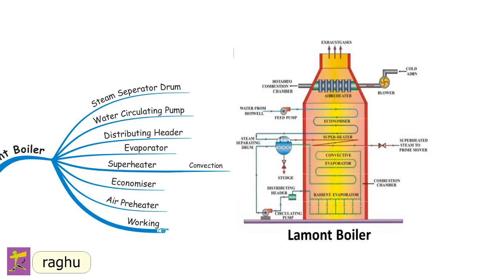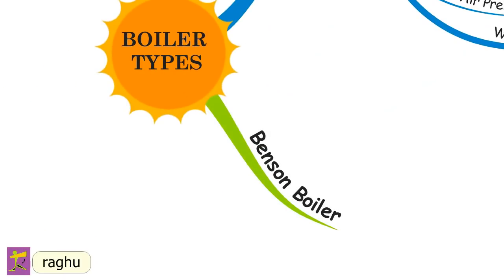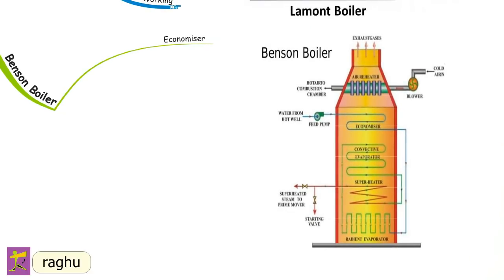In the La Mont boiler, the main difficulty experienced is the formation and attachment of bubbles on the inner surfaces of heating tubes. These attached bubbles reduce heat flow and steam generation by offering higher thermal resistance than a water film. This difficulty is overcome in the Benson boiler, which is the first type of drumless boiler — also called a once-through boiler. Feed water from the feed tank is supplied to the economizer, which preheats the feed water before it enters the radiant evaporator.